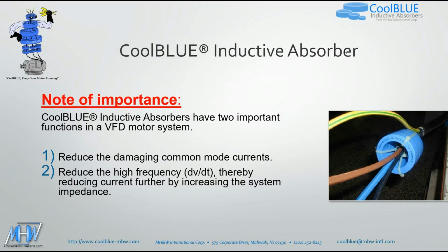A note of importance: CoolBLUE inductive absorbers have two functions in a VFD motor system versus just the one with the other solutions, which is just to divert the voltage. It reduces the damaging common mode currents, and it reduces the high-frequency dV/dt, thereby reducing the current further by increasing the system impedance. The high dV/dt was on that very first graph of the square wave, that sharp ringing. It will knock those ringing peaks down, which improves your system performance.